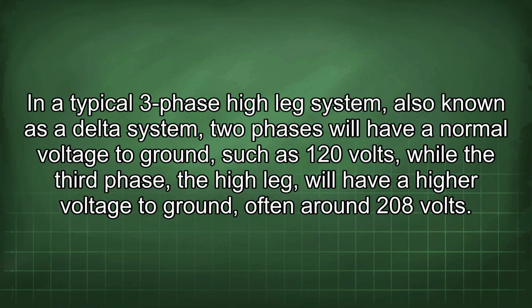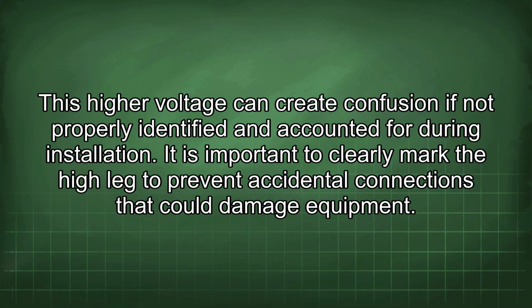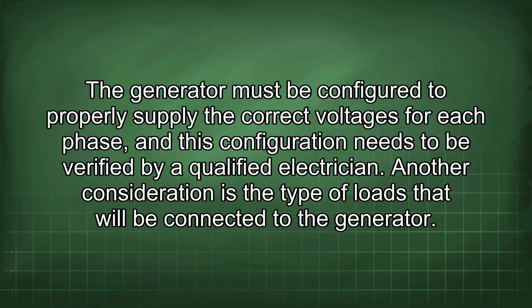In a typical three-phase high-leg system, also known as a delta system, two phases will have a normal voltage to ground, such as 120 volts, while the third phase, the high leg, will have a higher voltage to ground, often around 208 volts. This higher voltage can create confusion if not properly identified and accounted for during installation. It is important to clearly mark the high leg to prevent accidental connections that could damage equipment. The generator must be configured to properly supply the correct voltages for each phase, and this configuration needs to be verified by a qualified electrician.